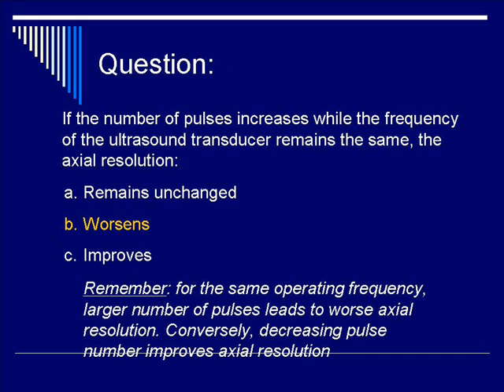Remember, for the same operating frequency, a larger number of pulses will lead to worse axial resolution. Conversely, decreasing the pulse number will improve the axial resolution.